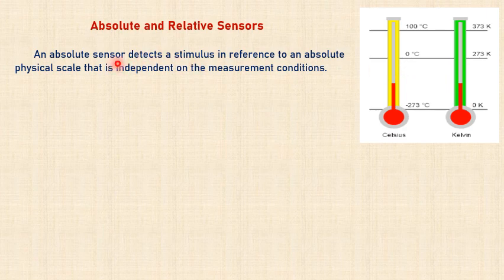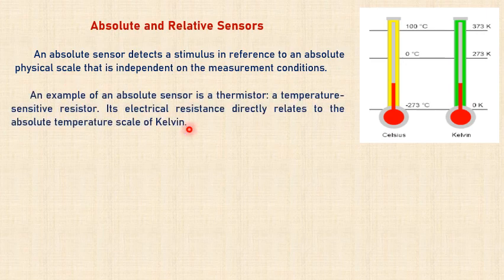Coming back to the definition, an absolute sensor detects a stimulus in reference to an absolute physical scale. So if temperature change is the stimulus, that is in the absolute scale. The best example of an absolute sensor is the thermistor, a temperature-sensitive resistor, whose electrical resistance directly relates to the absolute Kelvin temperature scale. So the thermistor can be called an absolute sensor.